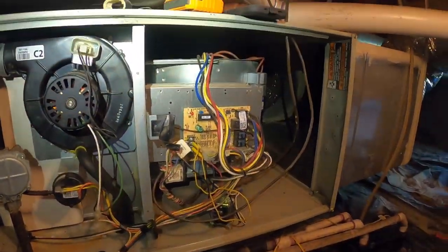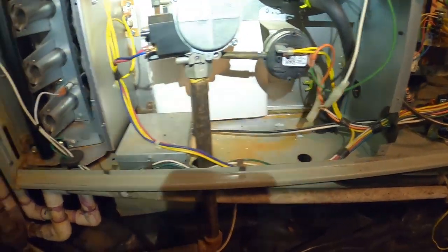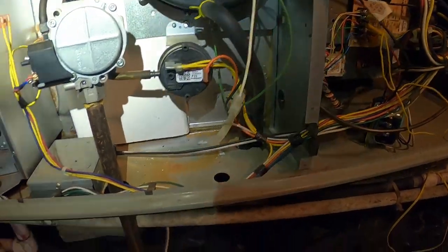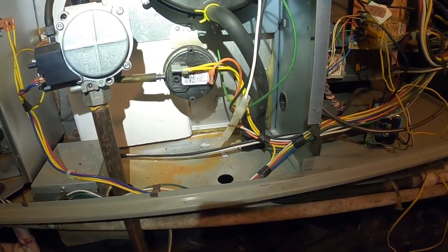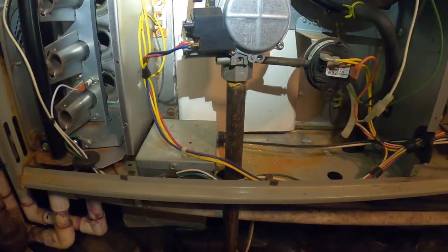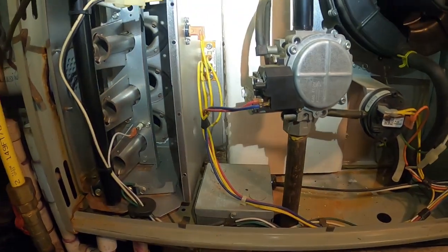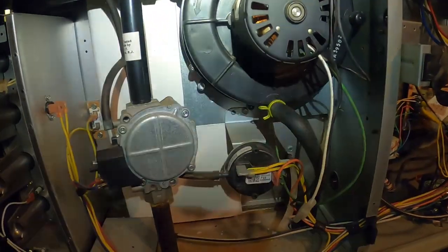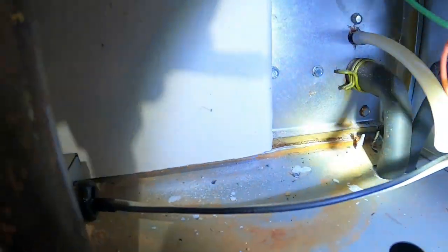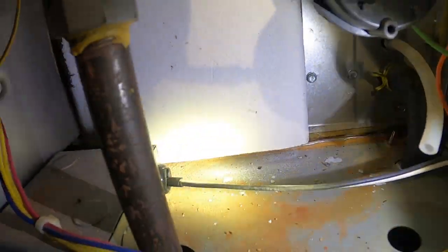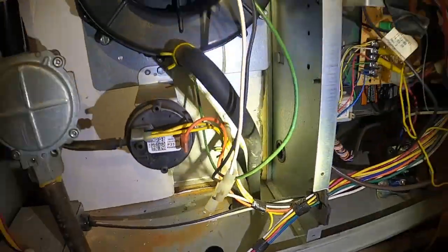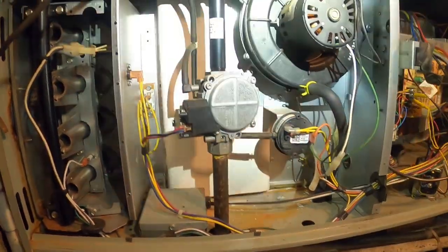Oh yeah, back in there is rust. Bottom is rust. So if you're familiar with this furnace and its drainage issues, keeping it clean and keeping the drain lines clean helps. But there's an issue on these furnaces that usually happens around the 13, 14, 15 year mark. I'm getting ready to show you what it is and why you find that acidic water, corrosion, and rust across the bottom of these older Trane TUC 90% furnaces.